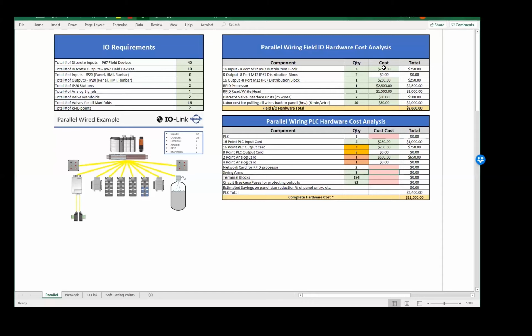A swing arm. Swing arms, for those of you that aren't familiar, are a way to more easily terminate those hard home run cables coming into the panel. They terminate on a terminal block base with a D-sub connection directly to the PLC card. It just saves a little bit of labor. A lot of labor, yeah. So we need 8 swing arms to take care of all of our I.O. cards in the PLC. And we'll say those are roughly about $175 apiece.